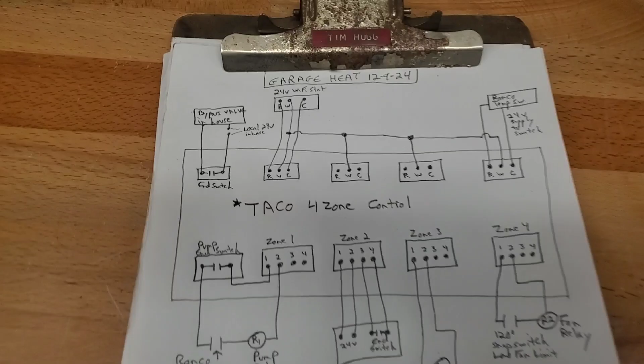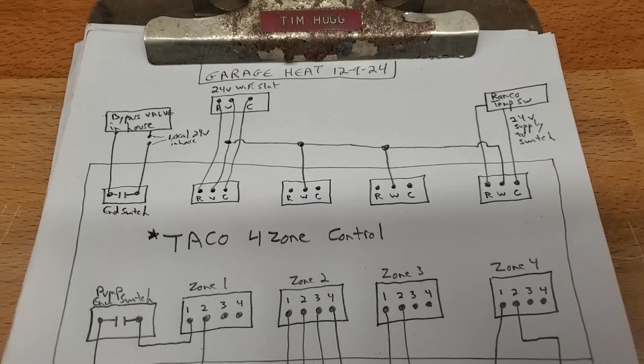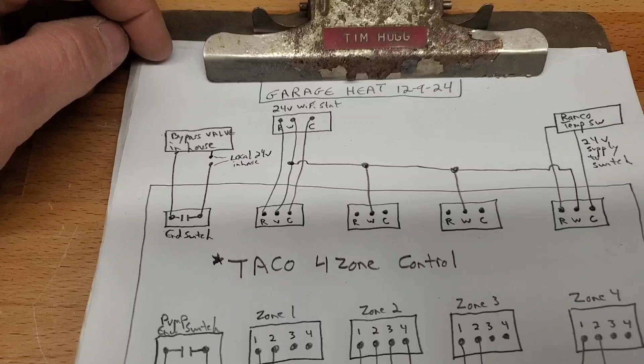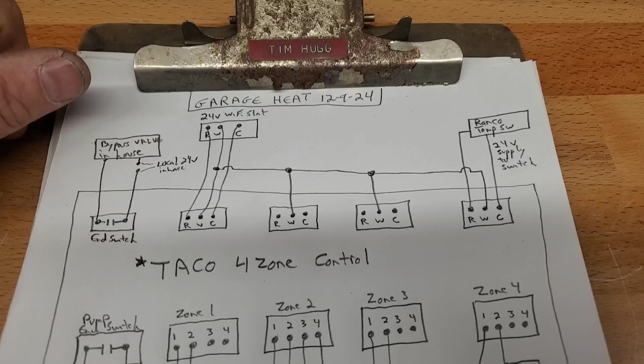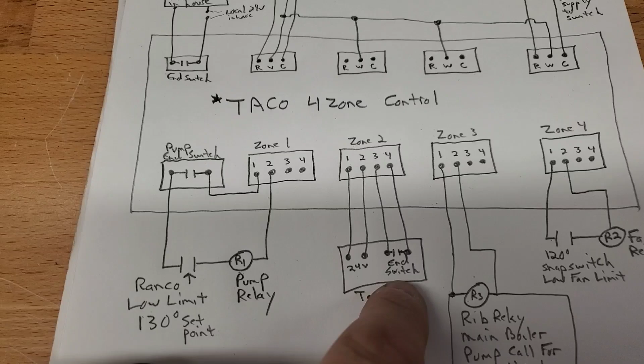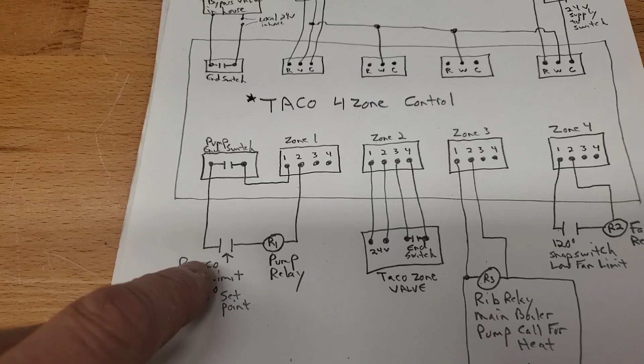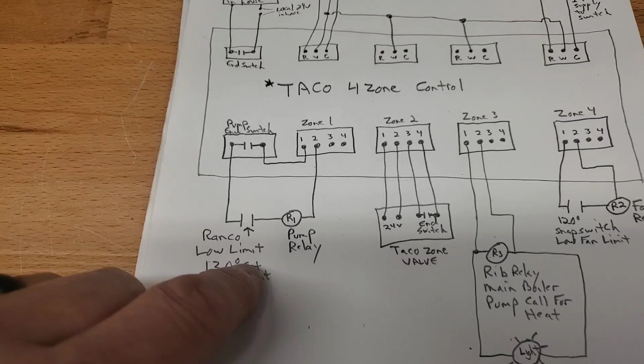And I'll show you the sequence of operation. I upgraded my control drawing on here, and what we got is our Taco 4-zone control. It's not being used conventionally; it's being used more as a relay center. When my garage thermostat calls for heat, that'll close. I got this jumpered so it closes all 4 of these zones. That supplies 24 volts to my 24 volt Ranco switch. And when that calls for heat, my zone valve opens and closes the end switch. So that'll close this end switch, and then it'll send power to the Ranco. As soon as the water temperature hits 130 degrees, it'll pull in the pump relay, and that'll activate the pump.